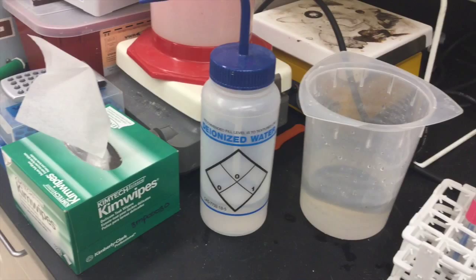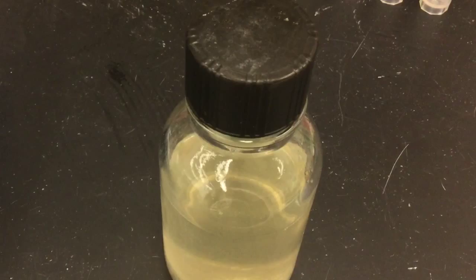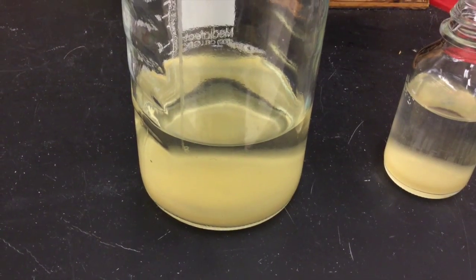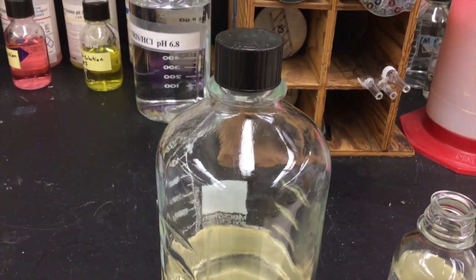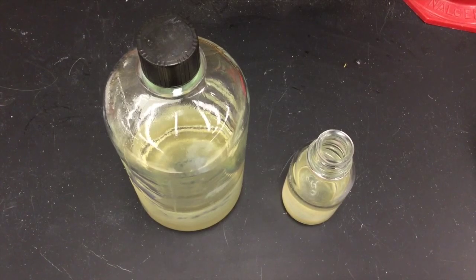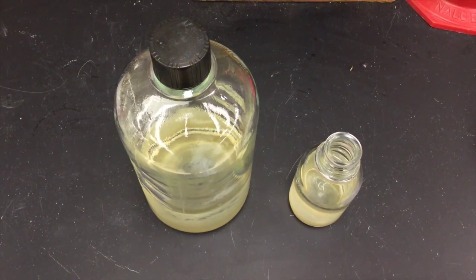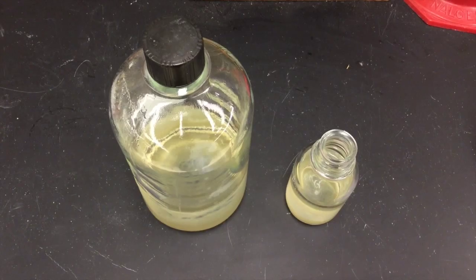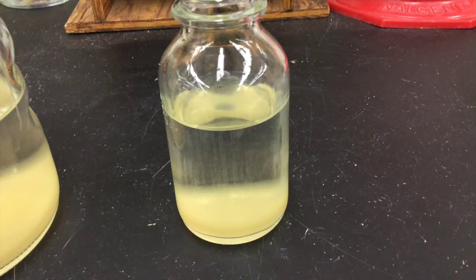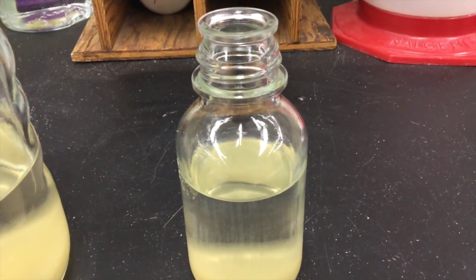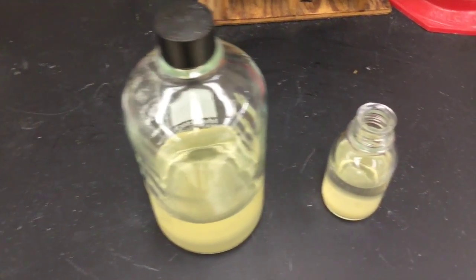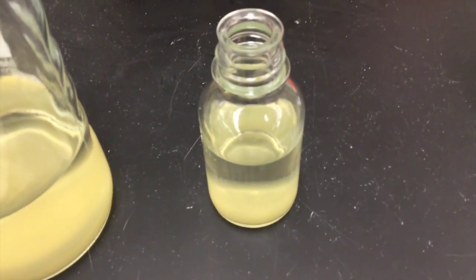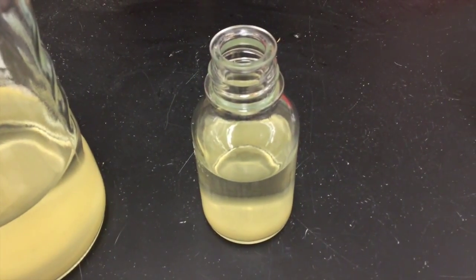To use the pH meter properly, you will also need Kim wipes, a squirt bottle of deionized water, a bucket, and a sample whose pH you wish to test. In this case, our sample is a medium in which we tried to grow algae. However, contrary to our predictions, nothing grew whatsoever. So we are going to test the medium's pH to see if anything went wrong during its preparation. If the solution is much too acidic or much too basic, that could be the reason that we didn't see anything growing. We have transferred some of the medium to a smaller container for testing.